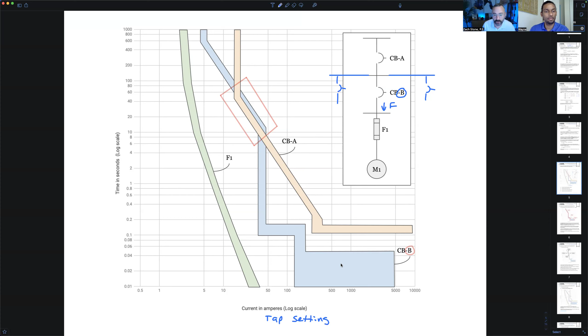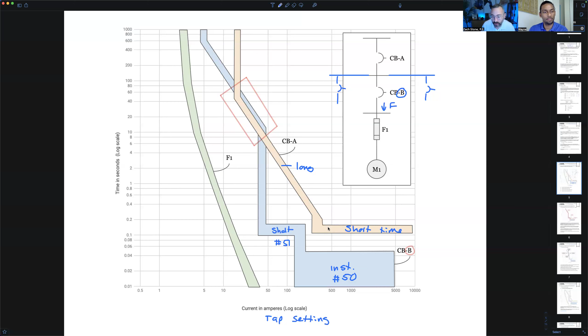So, shifting the tap setting. Let's pick on circuit breaker A. First of all, we've got three different regions. Circuit breaker A has a short time region and a long time region. Anything above breaker B, this is an instantaneous region. That would be like our ANSI 50. And then this is another short time region. That would be ANSI 51, no different from this week's class. And then this would be long time. And then this period would also be long time, another ANSI 51 function.